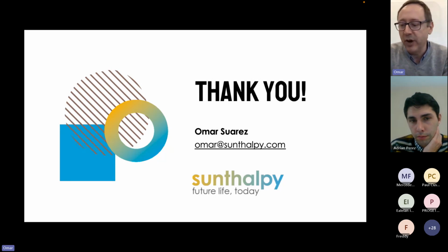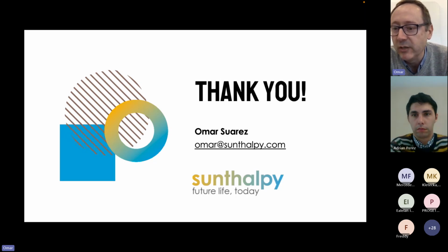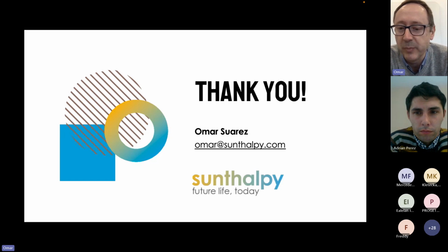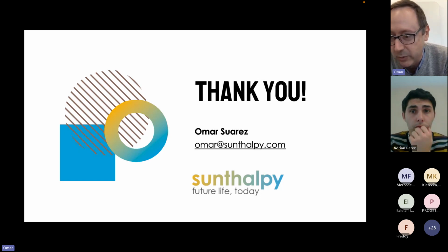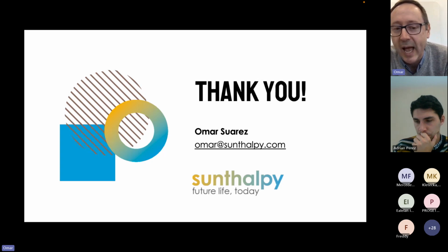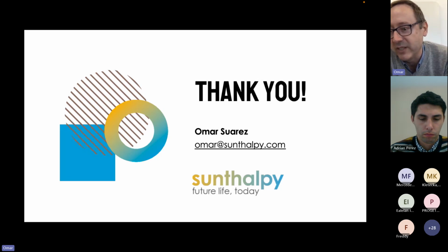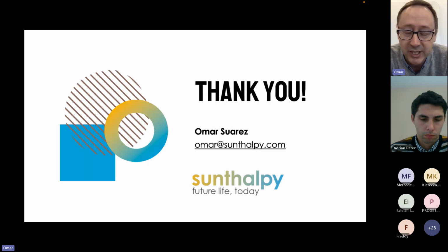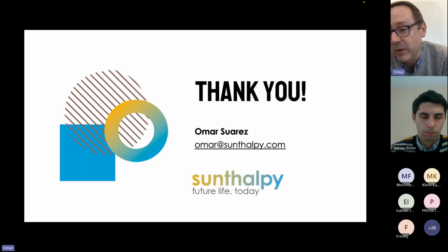Yeah, definitely. If you're able to provide the required heating in order to get a very good performance of the heat pump, you need to work with an operating temperature of the water below 35 Celsius. If you operate higher, that's not low enthalpy, and the performance of the heat pump will fall. If you have another radiator that works radiating, not convecting, with water at a lower temperature than 35 or 30 Celsius, then you will be able to get very good performance of the heat pump. And ideally, if it radiates, you will also activate the mass.